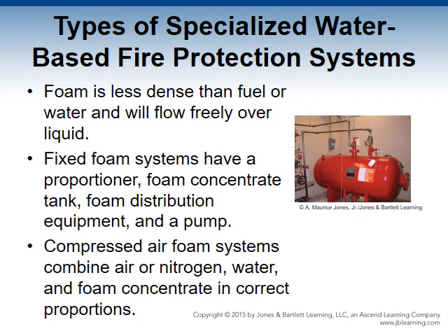Once the foam concentrate and water mixes to the foam solution, the solution must mix with air to form the bubbles. The process occurs by a mechanical means. The foam products fall into three general categories, and that's low expansion, medium expansion, and high expansion. And that basically refers to the amount of bubbles you're going to get.